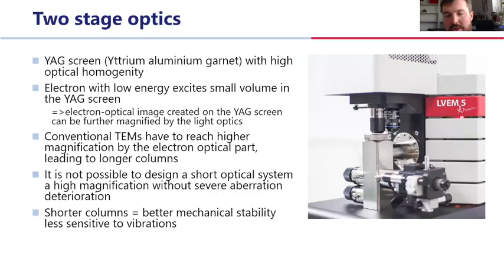In low voltage TEM, the situation is completely different. The excited volume in the screen is much smaller because of the low energy of the electrons. This means each pixel of the image on the screen is also much smaller. So we can magnify it optically much more before reaching this empty magnification. And to make the system even more versatile, we include a carousel with exchangeable optical objectives, so users can easily switch between different levels of magnification depending on their application.